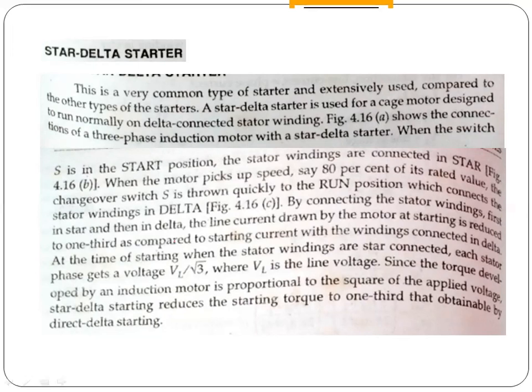At the time of starting, when the stator windings are star connected, each stator phase gets a voltage of VL by root 3. That means we know that in star connection, VL equals root 3 times V phase. That means the phase voltage equals VL by root 3. So when it is star connected, it gets VL by root 3. Our phase voltage is root 3 times lesser, and for that reason, as the torque is directly proportional to the square of the voltage, the developed torque of the three-phase induction motor will also be reduced to one-third.